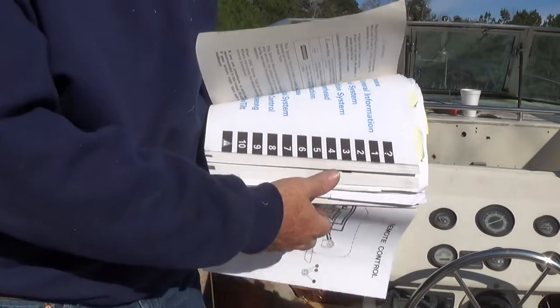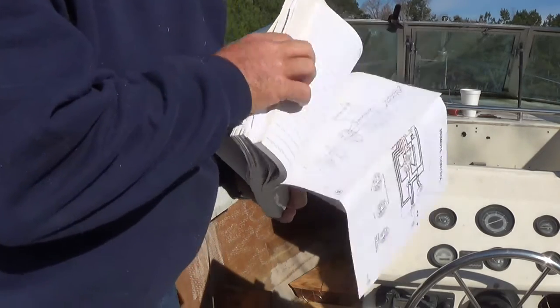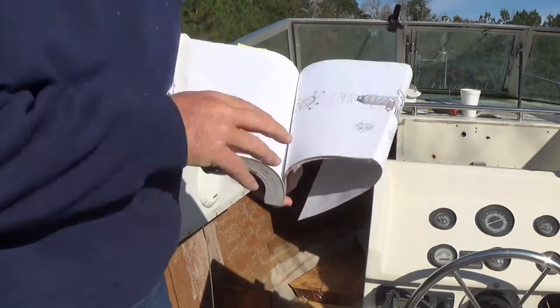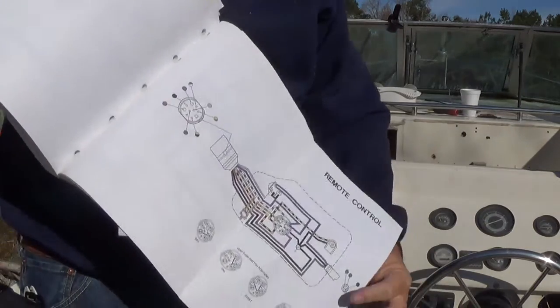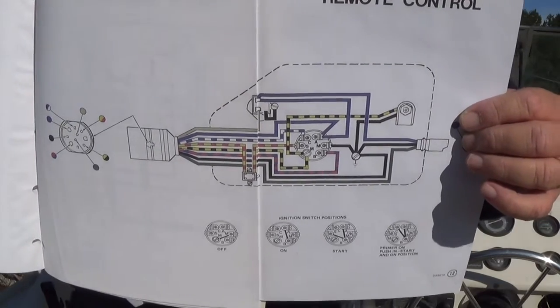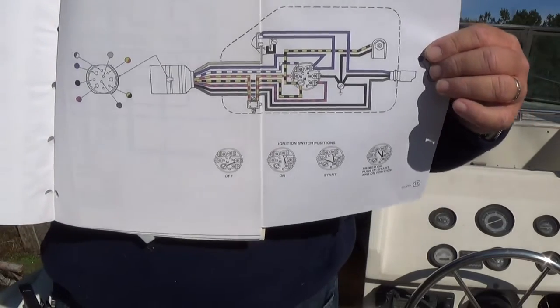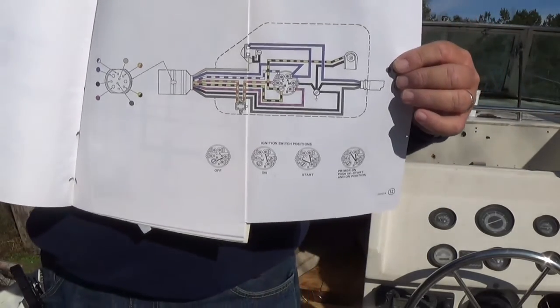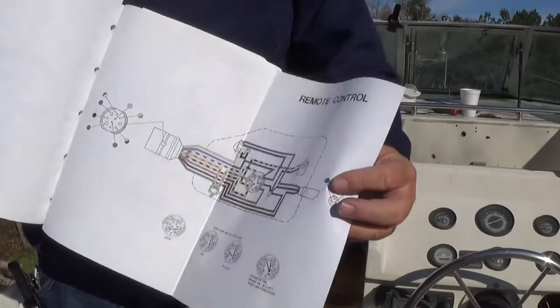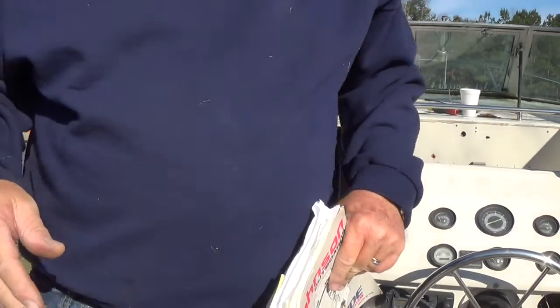Okay, what I'm doing here is I just wanted to verify that all those plugs and everything on the... What I'm doing here, as you can see, I'm going back to the switch, and I'm going to the plug-in on the motor. This is a wiring diagram, and I'm going to trace those back just to verify that each wire is on the proper terminal on the switch. I think they are, but I want to be sure they are, so I'm going to take the time to do this.